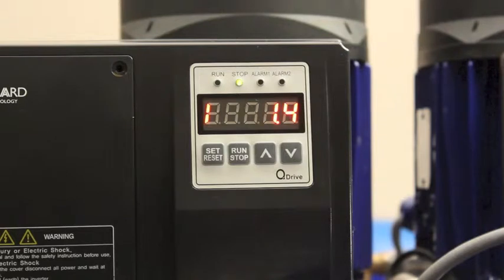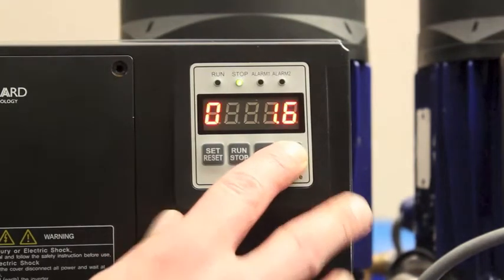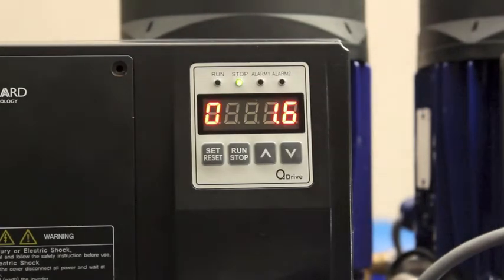To change the pressure reading on I and O, we first need to make a note of which transducer needs adjusting and how much it needs adjusting by. So for example, if the inlet I is showing 1.4 bar and the outlet large O is showing 1.6 bar, the outlet transducer needs to be adjusted by minus 0.2 bar.